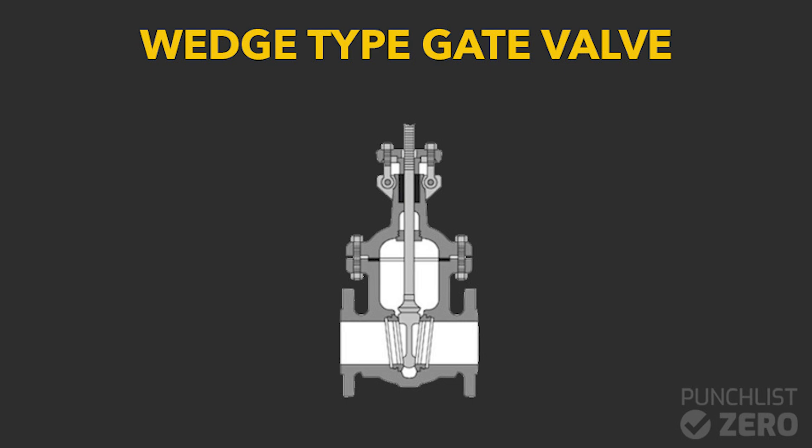The wedge type consists of two inclined seats in the shape of a wedge, and they are usually used in high flow or turbulent applications like steam service. Seating pressure on both sides makes the wedge type gate effective for low pressure applications as well. Wedge material can be solid, flexible, or split.